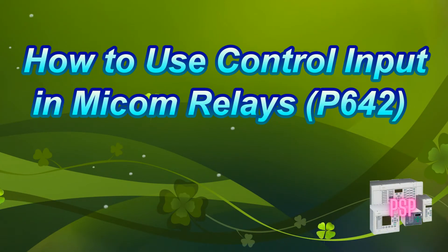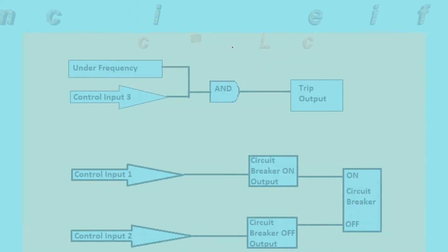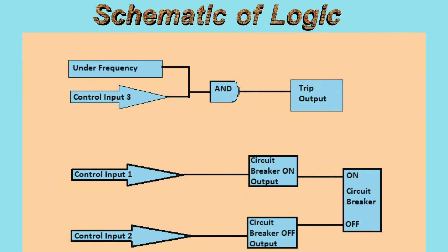Welcome to my channel PSP Protek. Today we will see how to configure control inputs in MiCOM relays. We have a P642 relay and today we will design two logics: one is to take the under frequency element tripping output, and another is the breaker control. For breaker control we will use control input one and two — one for on and two for off — and control input three will be used to enable or disable the tripping output of the under frequency relay.